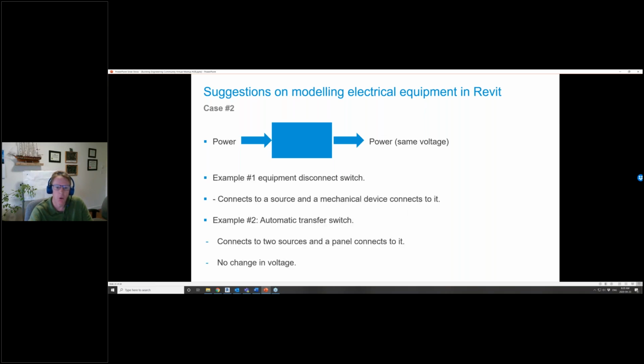So we use it here for an equipment disconnect switch. Revit contains a part type, electrical equipment switch, but that part type is frankly useless because it doesn't support a downstream connection. So instead we model it as a panel with a number of output single pole breakers equal to the number of poles. For a three-phase device, we only allow it 3 poles of output breakers - in other words, one 3-pole circuit. Then we can connect that disconnect switch to a source, and connect a mechanical device downstream to the switch, and have it appear in our one-line diagram.